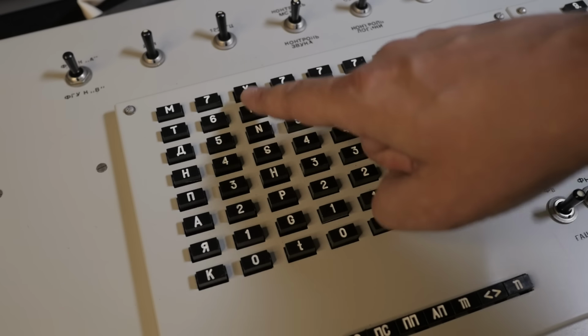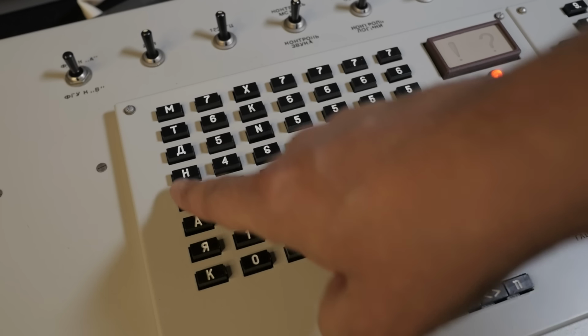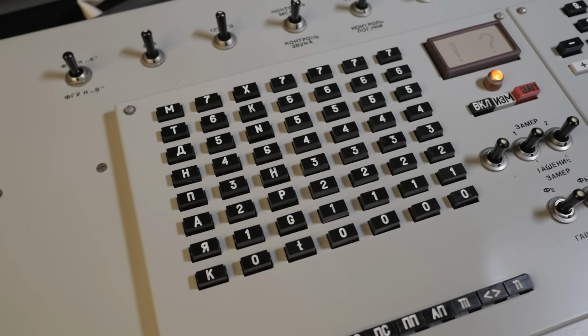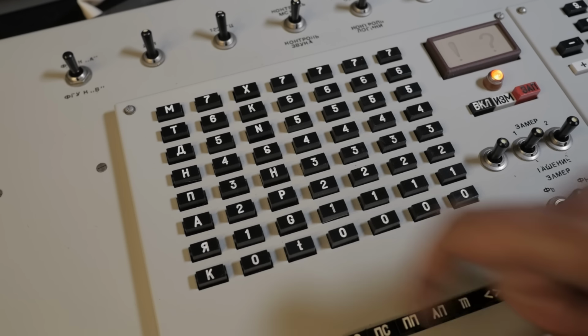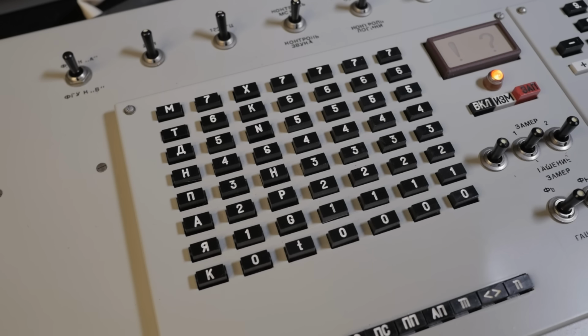So, to enter a request you press one button in each column. The code is built in a sense from something very broad to something extremely specific. It's like a funnel. I will use the reactor's thermal power as an example. The first column, containing Cyrillic letters, identifies a major system or big group of parameters. For example, A represents the reactor as a whole. T, as you already saw, represents the turbine. Then M refers to the turbine mechanical systems. N represents pumps, and so on.